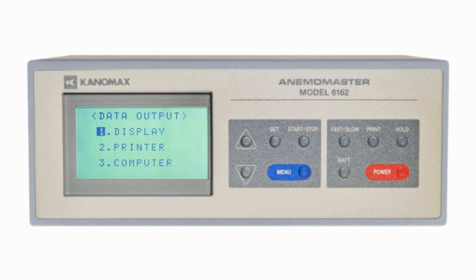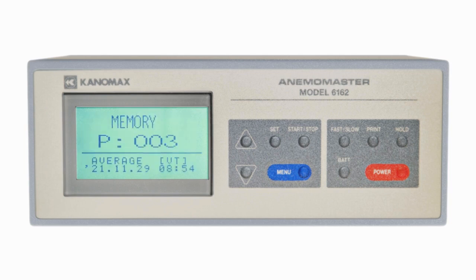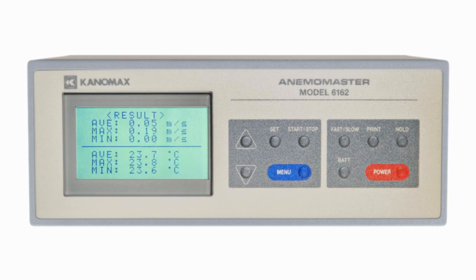Selecting display in the data output menu will show previous measurements. At the center of the screen is the page number, and below that is the measurement mode used for that reading, an indicator of what factor or factors were measured, and below that is the date and time. To display the data for that reading, press the Set key, and the results will appear on the screen.